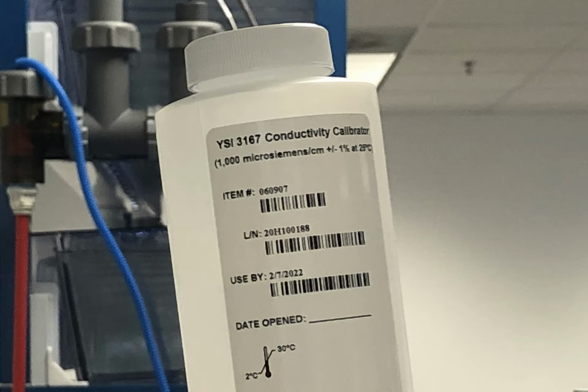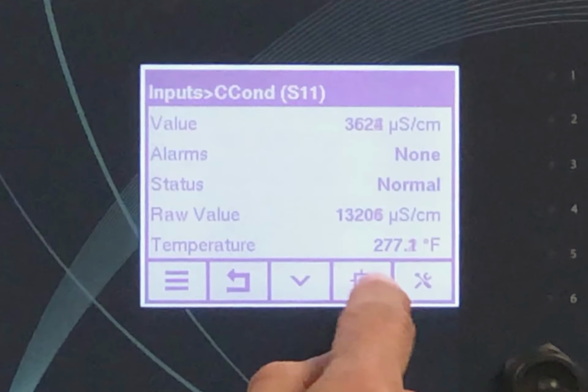Once the sensor has been cleaned, place it in a beaker with a conductivity standard solution or other known conductivity value solution, ensuring that any air in the hole of the sensor has been eliminated. Enter the calibration mode in the controller and verify proper operation.